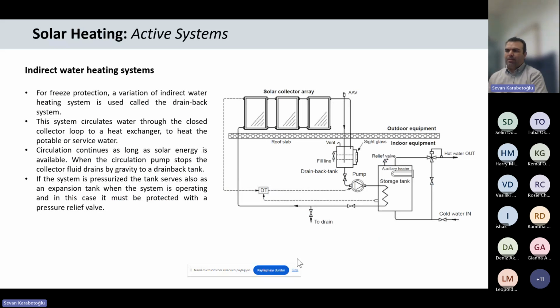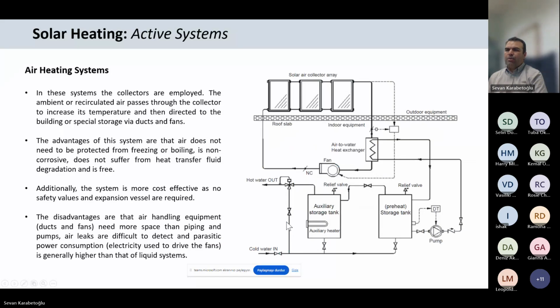Then a drain back system is implemented for indirect water heating systems. This system circulates water through the closed collector loop to the heat exchanger, to heat the potable or service water. Circulation continues as long as solar energy is available, and when the circulation pump stops, the collector fluid drains by gravity into the drain back tank. If the system is pressurized, the tank serves as an expansion tank, and in that case it must be protected with a pressure relief valve, because we don't want to get back to the drain back tank. So these are the indirect and direct circulating water systems.